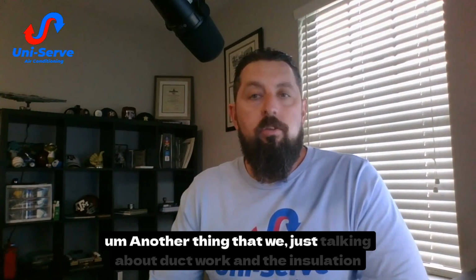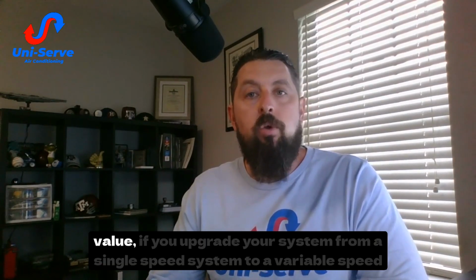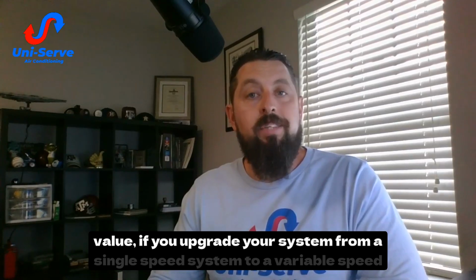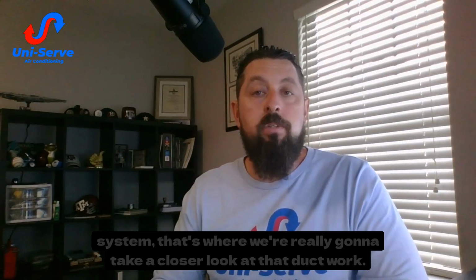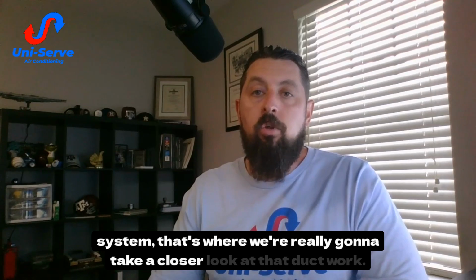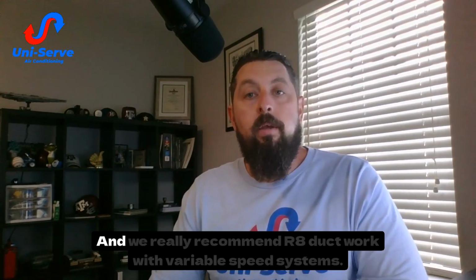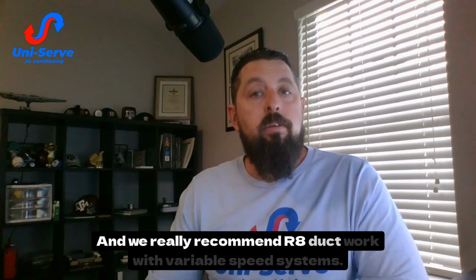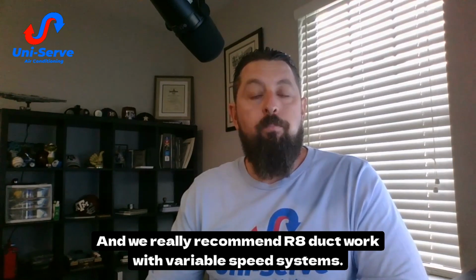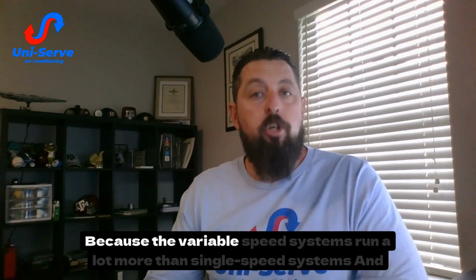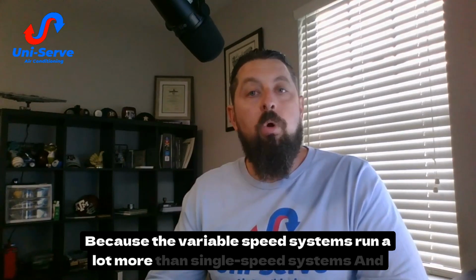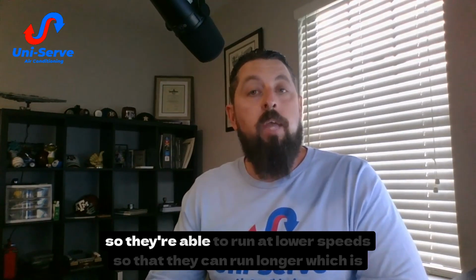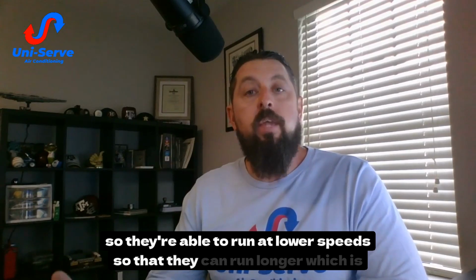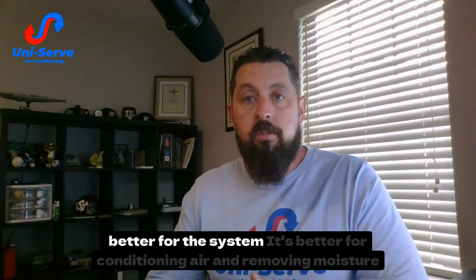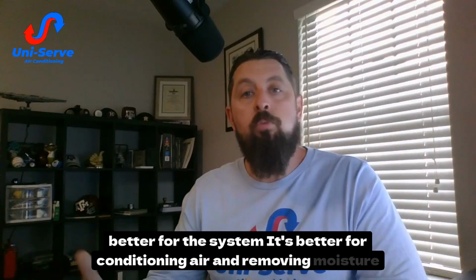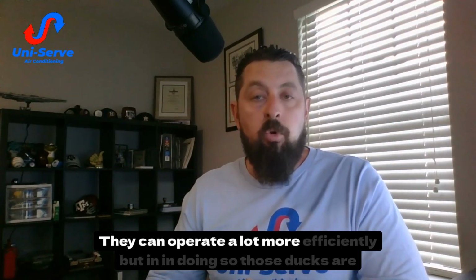Another thing, talking about ductwork and the insulation value: if you upgrade your system from a single speed system to a variable speed system, that's where we're really going to take a closer look at that ductwork. And we really recommend R8 ductwork with variable speed systems. The reason is that variable speed systems run a lot more than single speed systems. They're able to run at lower speeds so that they can run longer, which is better for the system. It's better for conditioning air and removing moisture. They can operate a lot more efficiently.